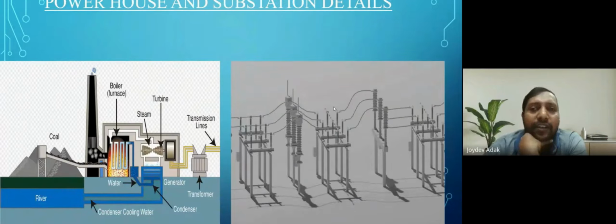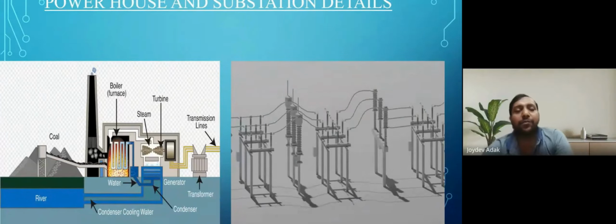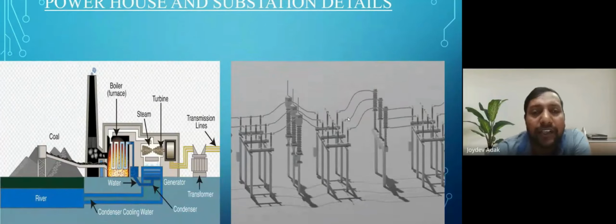Based on the scheme of the substation, whether it is a single main bus scheme, a two main and one transformer bus scheme, a single main and one transformer bus scheme, or a one and a half breaker scheme, there will be different switching equipment. A bay is the set of equipment utilized for carrying power from source to destination.